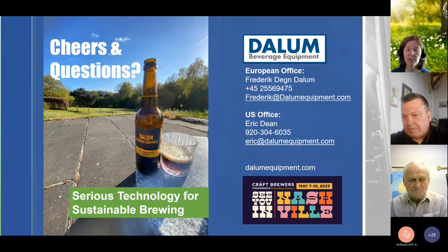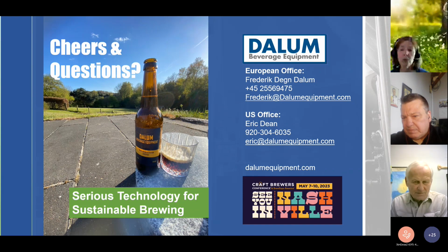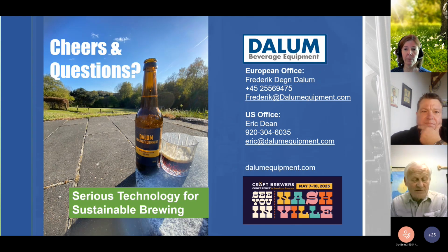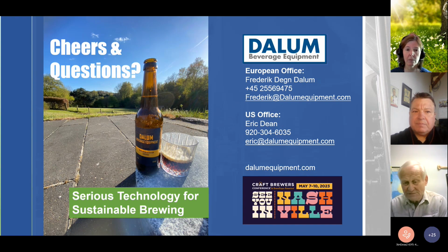Okay. The next part of the question is, with glycol being used to cool the incoming CO2, can you also use glycol to vaporize the CO2 for use? You know, capture the free cooling and save the vaporization energy. Yes, certainly. Some people do it. One brewery I worked at was actually using it for chilling water down. You have to obviously watch out for the freeze point. But if you have enough flow on the water side of the heat exchanger, you can actually use the vaporizing to chill the water down. You could use glycol also. It wouldn't matter. But yes, you definitely can collect energy off of it.